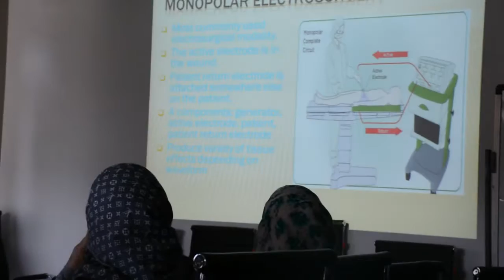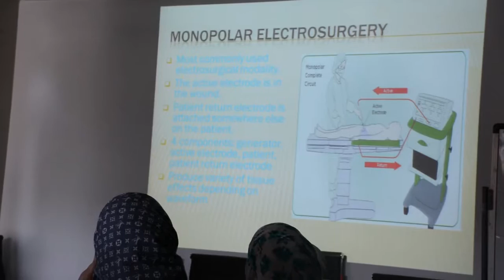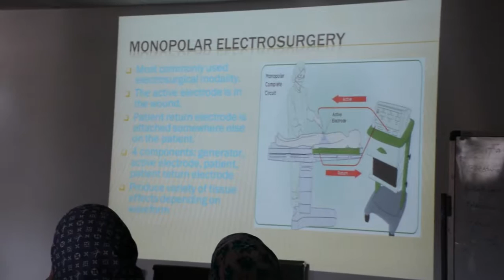Energy devices in surgery. Monopolar electrosurgery. Most commonly used electrosurgical modality. The active electrode is in the patient, and the patient return electrode is attached somewhere else on the patient. Four components: generator, active electrode, patient, and patient return electrode. It produces a variety of tissue effects depending on waveform. Tissue effects with waveform modification.